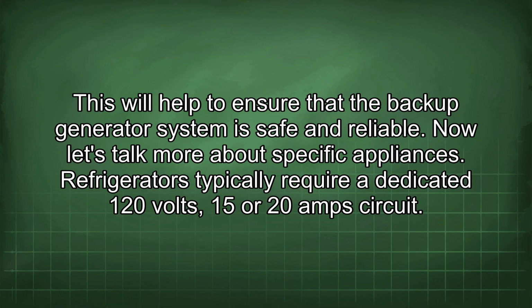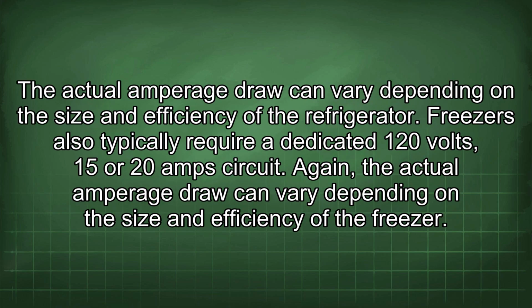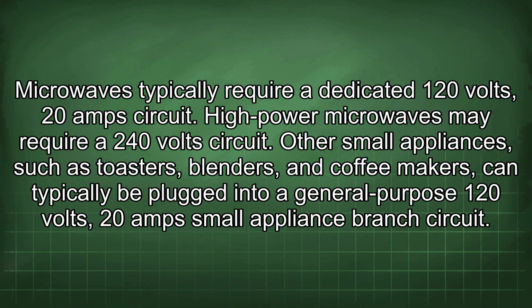Now let's talk more about specific appliances. Refrigerators typically require a dedicated 120 volts, 15 or 20 amp circuit. The actual amperage draw can vary depending on the size and efficiency of the refrigerator. Freezers also typically require a dedicated 120 volts, 15 or 20 amp circuit. Again, the actual amperage draw can vary depending on the size and efficiency of the freezer. Microwaves typically require a dedicated 120 volts, 20 amp circuit. High-power microwaves may require a 240 volt circuit.